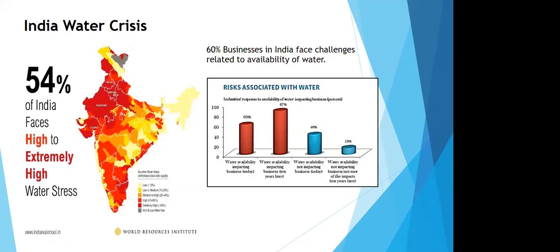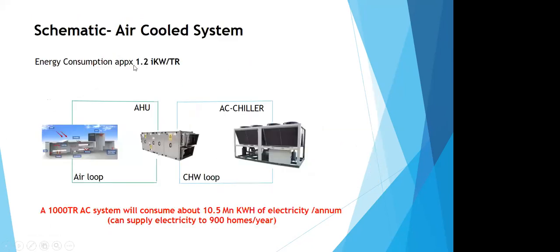Well, before I go to adiabatic coolers, people would argue, why don't we use air-cooled systems instead of water-cooled systems? And we can get rid of the menace of water. So there is a drawback to the air-cooled system as well. So let's look at how the air-cooled system works. We have got rid of the cooling tower over here. We put an air-cooled chiller, which is plug and play, and we just have two loops. We have the chilled water loop and we have the air loop. So we can simply connect the chiller, provide the chilled water to the air handling unit, and the air handling unit can provide chilled air to the heat load of the occupied space.